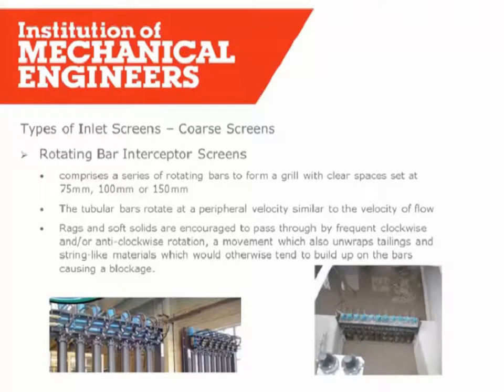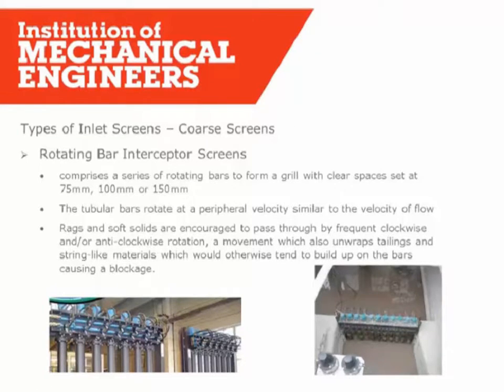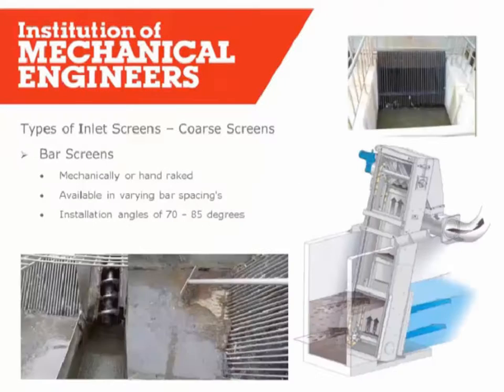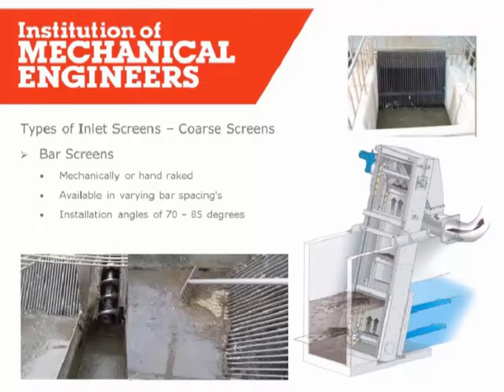Moving on to types of inlet screens, starting with coarse screens. We have rotating bar interceptors, commonly known as RBIs - a series of rotating bars forming a grille across an opening in an inlet channel. The bars rotate at a peripheral velocity similar to the flow velocity and gently pass through screenings that would be acceptable to a fine screen, while preventing large objects such as timber from passing forward. One key thing to remember with RBIs is that you need a mechanism to remove the accumulated material from the channel. Similarly, with coarse screens we have bar screens - bar spacing can vary: 10, 12, 20, 25, or 50mm. These can be manual or automatic and are provided to prevent large gross solids from damaging fine screens.